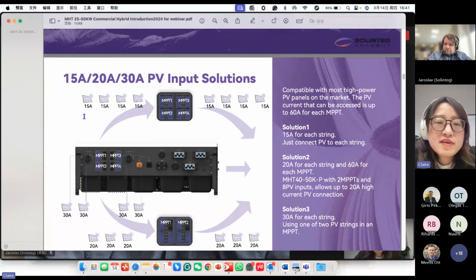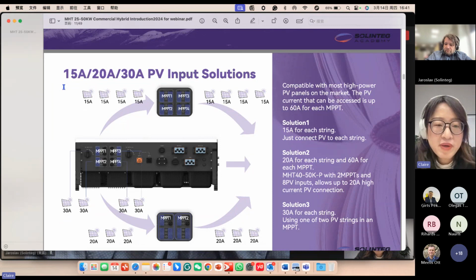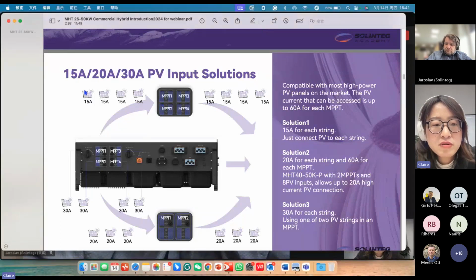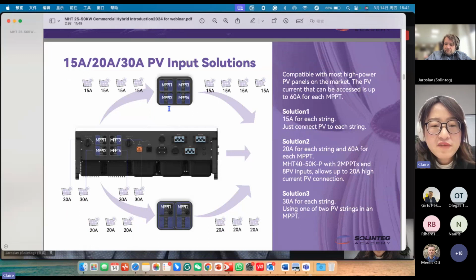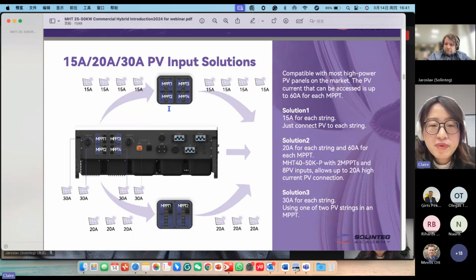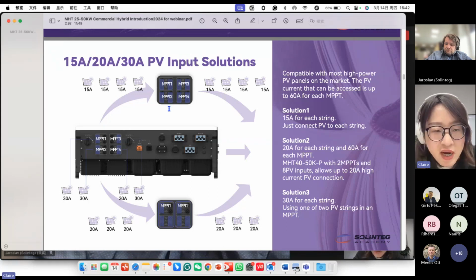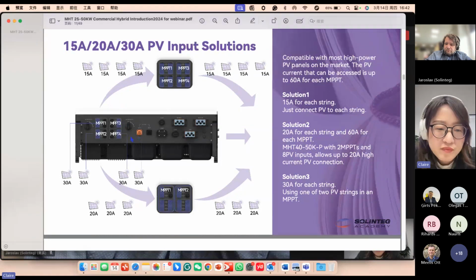Now here you can see this is our solution for different PV panels. For the normal 15 ampere PV panel, we can directly connect it to the PV strings of our inverter. Here you can see this is a 4 MPPT version inverter. There are 2 PV inputs in each MPPT. So just connect all the PV strings to every PV input, so we can support a 15 ampere PV connection. And if the customer uses bifacial panels or some high power panels with the PV output current over 15 amperes, they can have another solution.